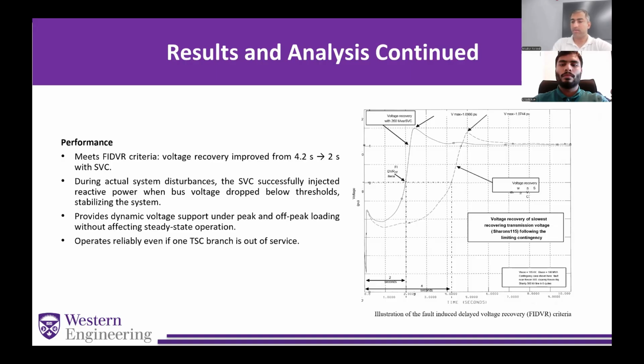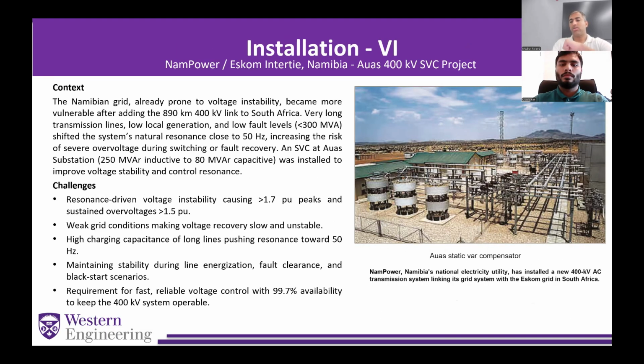As you can see from the attached picture, that's an illustration of fault-induced delayed voltage recovery, FIDVR, criteria. You have voltage recovery at the slowest recovery transmission voltage. So it shows all the analysis of the performance, and you can see the results as well, how the SVC improved the system. So now moving on to the next installation, that is going to be our last installation as well, installation 6, that is NamPower and Eskom Intertie.